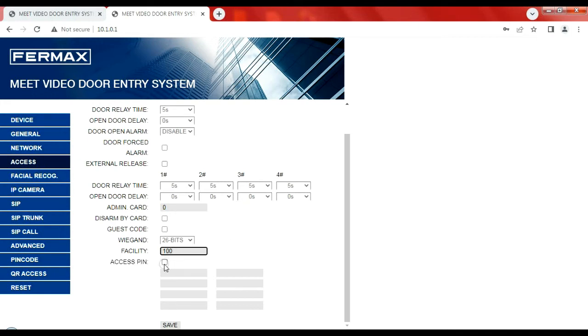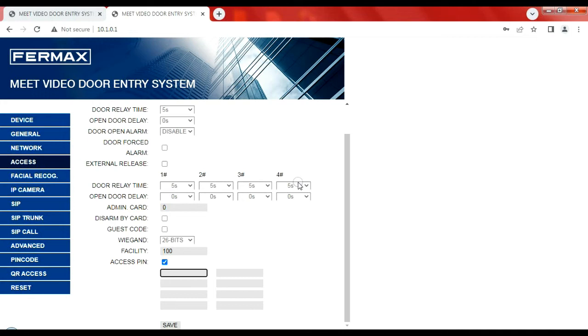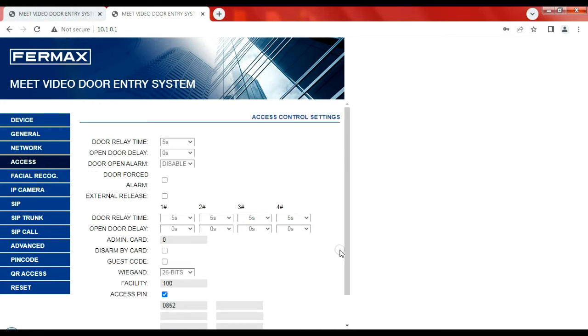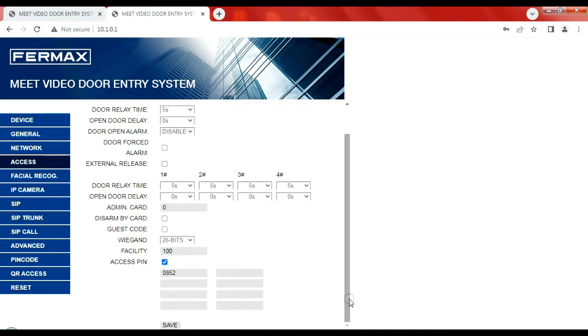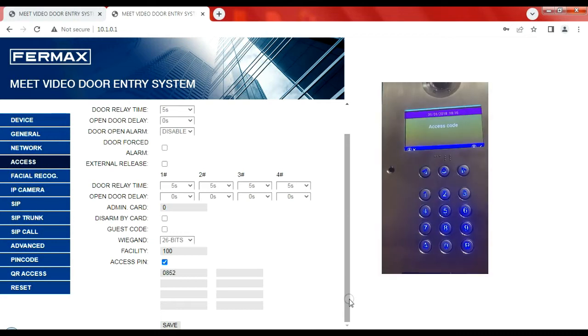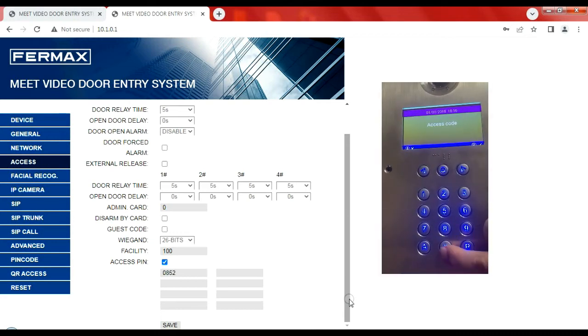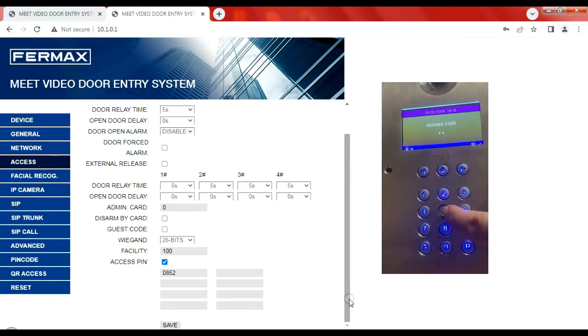Next would be access pin. So that's if you are going to use the onboard keypad as access control keypad. So again, small installation, you can give them cards to get in. Or if you want to, you can give them a pin. You can give the residents a pin to let themselves in. So in this case, if we generate a code, maybe 0852, so they go up the middle of the keypad. That's the new code to get in. Press save. And now the access pin to open the door would be 0852. And on the keypad, on the panel, you'd press the right arrow, type in the code, press B, and it would unlock the door.